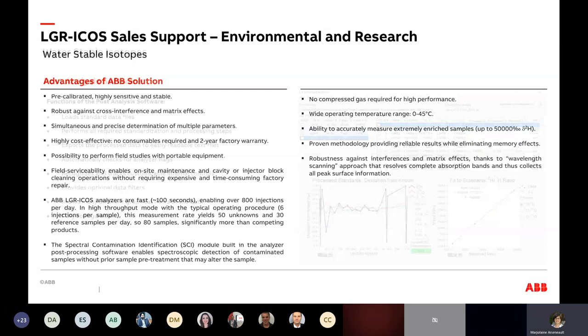To summarize the advantages of ICOS: it's pre-calibrated at the factory and highly sensitive using a laser diode. It's off-axis, rugged, and robust against cross interference because we're reading a very narrow band with a full spectrum measurement, which resists matrix effects — very important for hydrology and biology samples. It's highly cost-effective with no consumables, and comes with a two-year warranty. We're very confident in our technology.